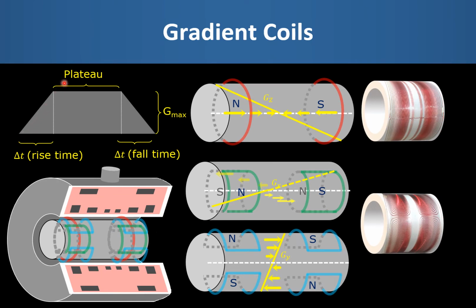Gradient pulses are generally trapezoidal in shape, and the gradient coils necessary to create them sit inside the room temperature bore of the magnet. The Z gradient is created using a Maxwell pair, so two counter-rotating currents, whilst the X and Y gradients are created using a quadrupolar design, otherwise known as a Golay configuration, with two north poles and two south poles. The X and the Y gradients are simply rotated 90 degrees with respect to each other. In reality, modern gradient coils are considerably more complex in terms of their design, so our simple Maxwell pair are actually overwound at either end, whilst the Golay configuration has the typical fingerprint type designs. These designs improve the efficiency and linearity of the gradient coils.